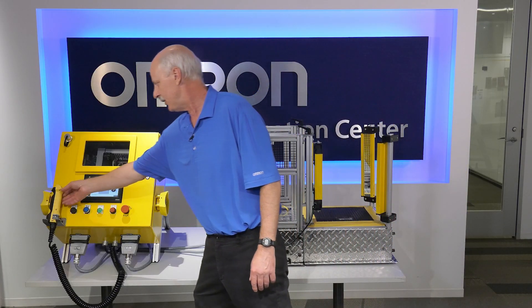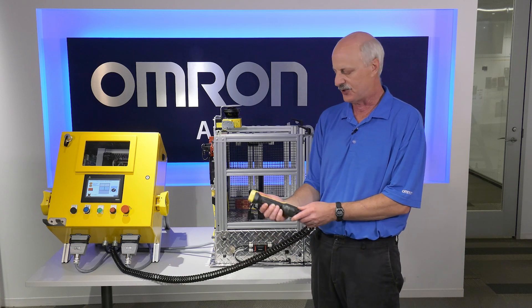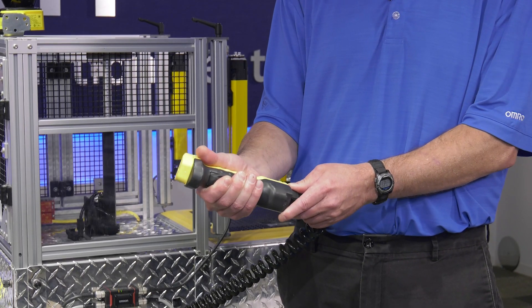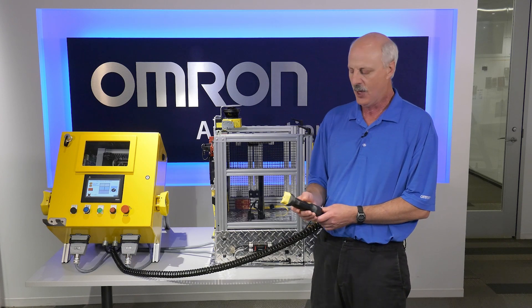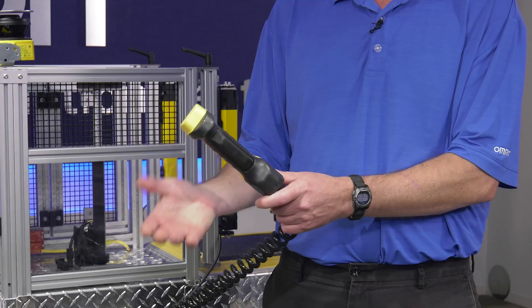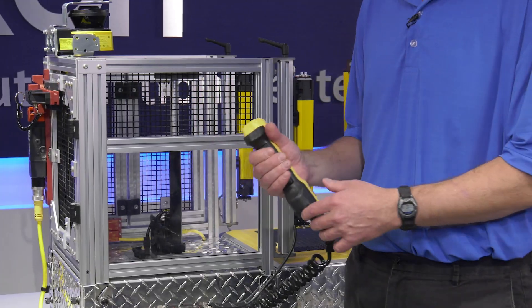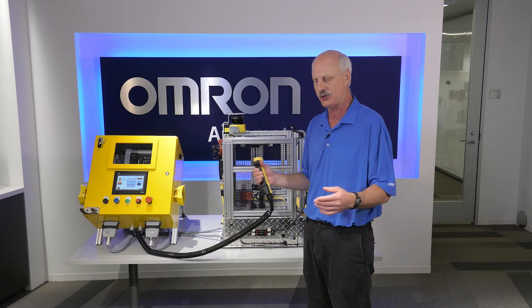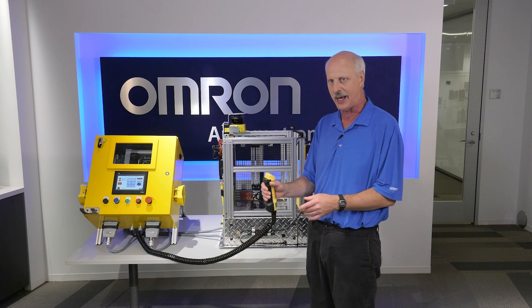The next item is our A4EG enabling switch. The switch has three positions: a release position, a holding state, and a grab state. You would use this in a robotic application — when it's in a fully relaxed or fully squeezed state, it stops the machine. But if you hold it in the half state, it enables the ability to run certain portions of the machine deemed safe while someone is close to the hazard. You can also get the switch with an emergency stop push button on it.